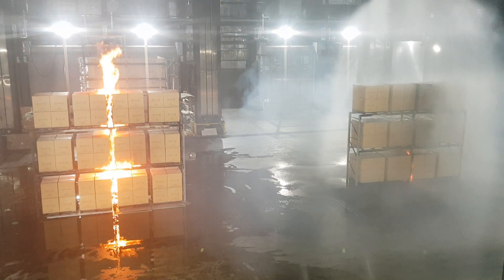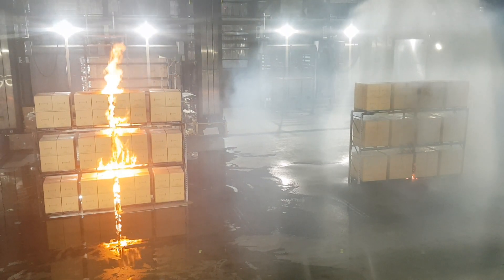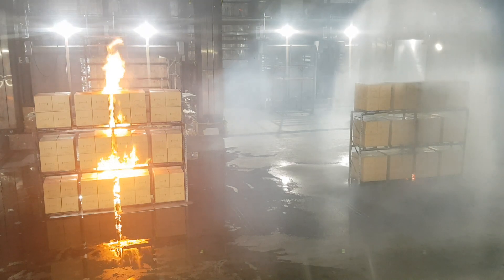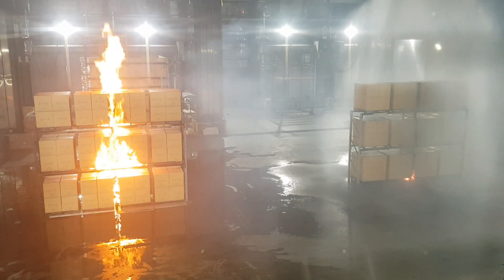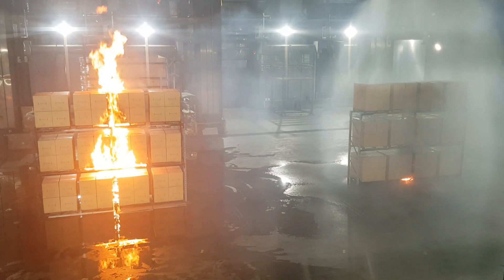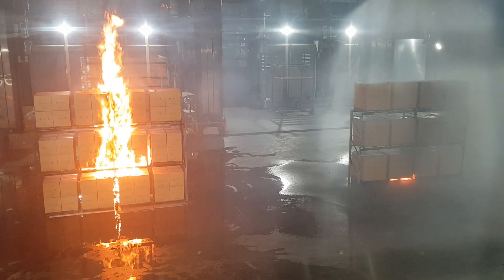We're not even one minute into the test. Above the sprinklered test, the gas temperatures are below 90 degrees Fahrenheit. And above the unsprinklered test, we're reaching temperatures as high as 300 degrees Fahrenheit at the ceiling.